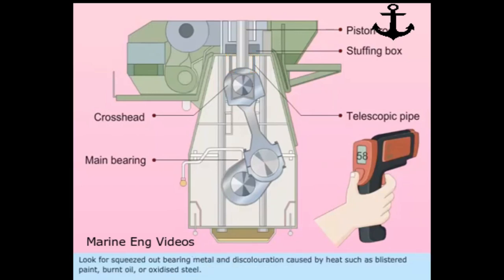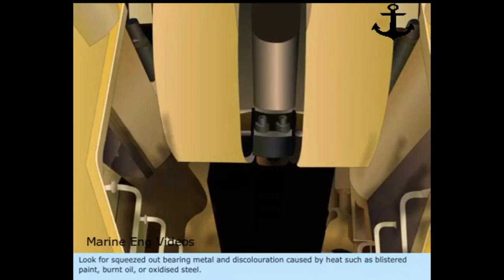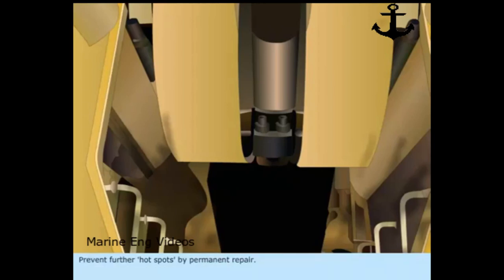Look for squeezed-out bearing metal and discoloration caused by heat, such as blistered paint, burnt oil, or oxidized steel. Prevent further hot spots by permanent repair.